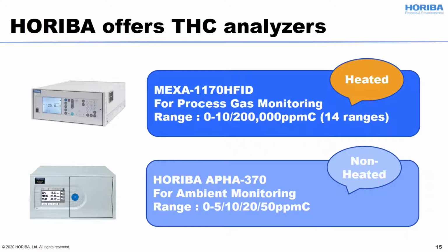We have another analyzer which is non-heated, model APHA-370. This was developed for ambient monitoring, which does not measure hydrocarbons containing high molecular weight hydrocarbons, so it doesn't have to be heated.